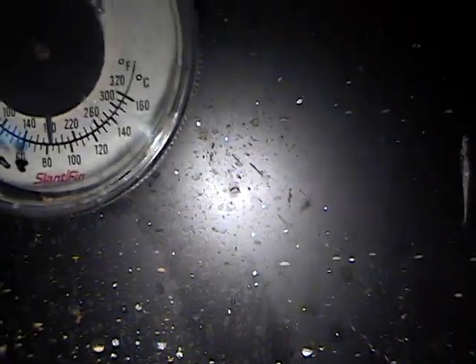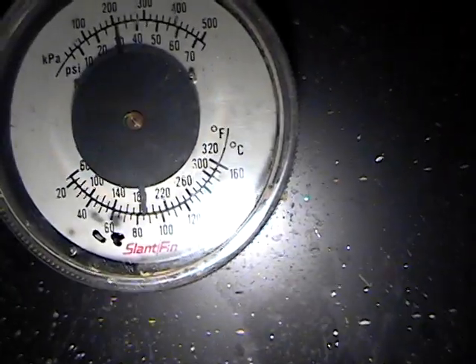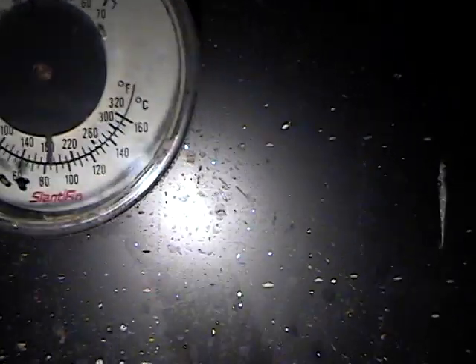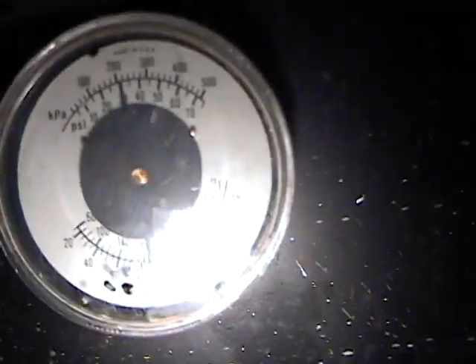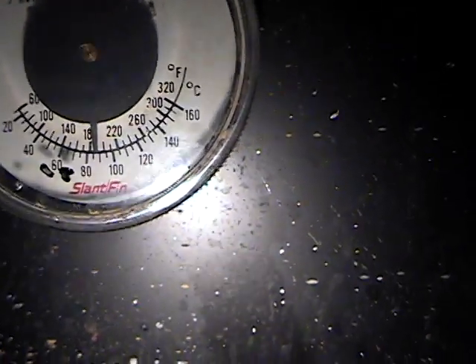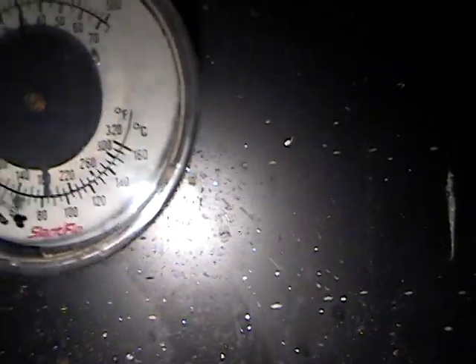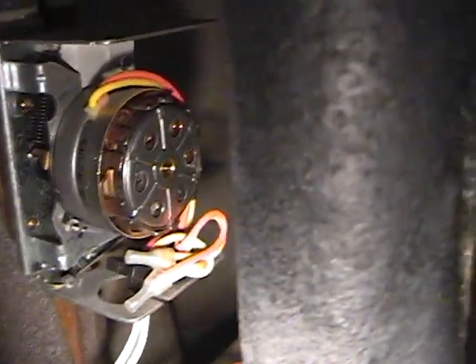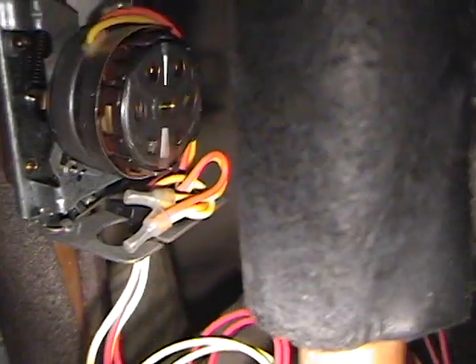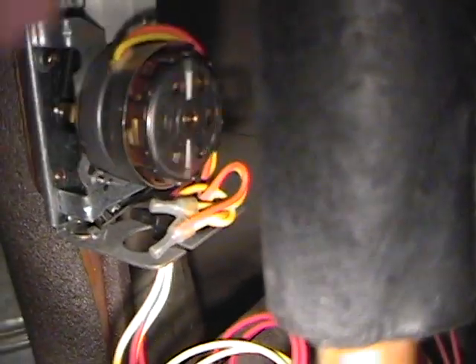So the temperature got up to about 190 degrees. So it was pretty close to the shutoff point, but like I said, when it hits 200 degrees, the burner cuts off, so that way the water's hot enough and it can just pump the water for proper heating. And see, if I turn it now, it just goes right back because of the springs.